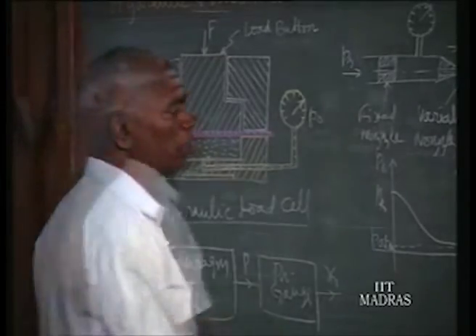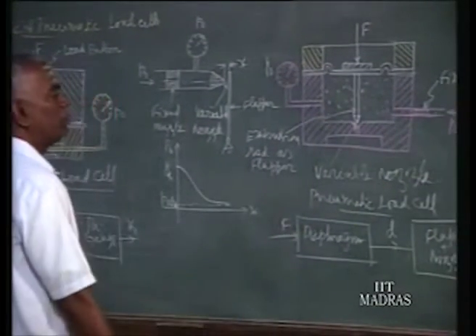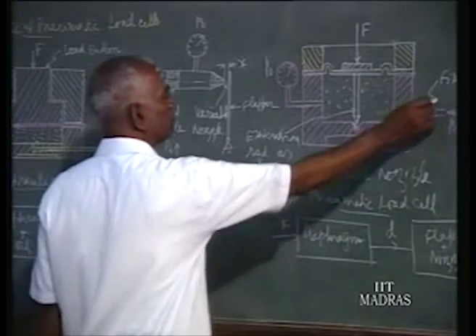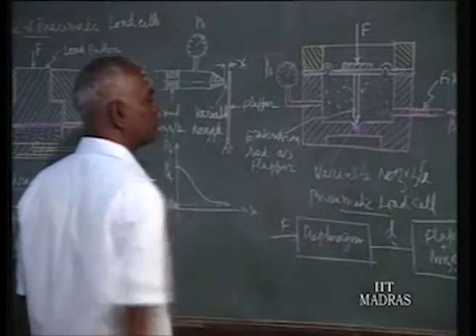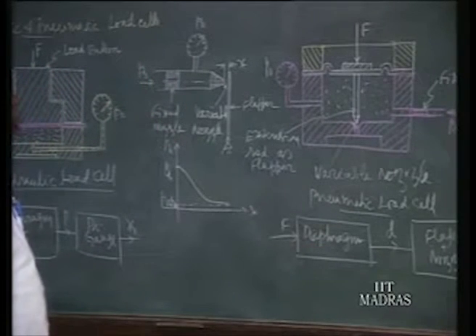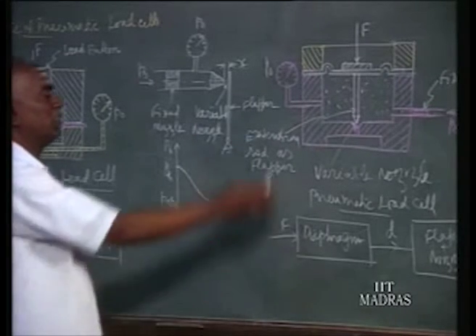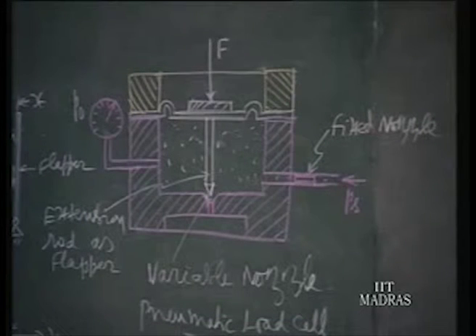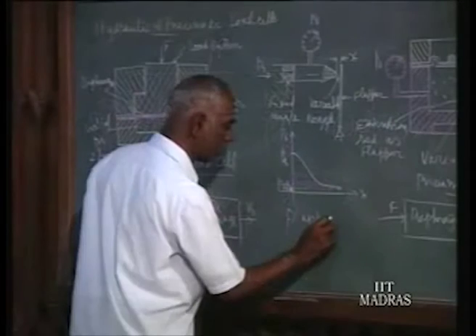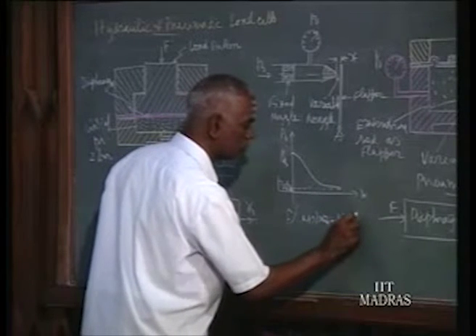Next we should see the pneumatic load cell. In the pneumatic load cell, the flapper nozzle principle is made use of. It is because air, compressed air, is a compressible medium, whereas liquid is incompressible. So the hydraulic one is a simple setup, whereas with pneumatic air or any gas, since the fluid is compressible, we are using the flapper nozzle principle.